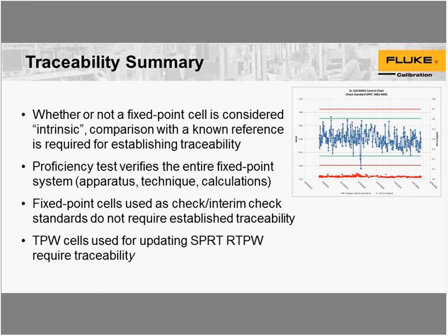If you're using a mini triple point of water cell to monitor industrial type PRT sensors, then an intercomparison could be performed using a PRT, as long as you recognize that you have to adjust the uncertainty so it's appropriate. You can then verify the triple point of water cell is working correctly with a calibrated SPRT, which in many industrial PRT cases is perfectly appropriate. The uncertainty will basically be a wash, so to speak, because of other more dominant uncertainties. So for secondary processes, this doesn't mean you have to have a full-blown intercomparison. We'll talk more about that in a few minutes.